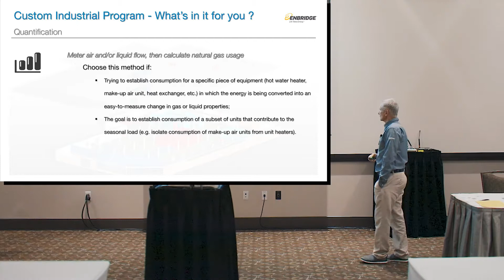So how would we do this here in this example? We would, for example, not use a meter on the makeup air unit. We would put an air balance study in place. The reason for that is that an air balance study can measure all your airflows for, for an average manufacturing facility, about $5,000 for, say, 6 or 7 makeup air units. And if I know the volume of air going through your makeup air unit, I can tell you within 5% what your natural gas usage is. So there's no point in metering all of those makeup air units.